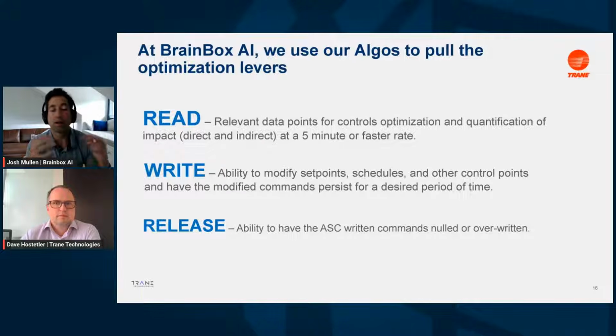And then finally, all advanced supervisory control should have guide rails, and it should have the ability to release control for whatever reason, whether it is internet connectivity, or some problem with the system as a whole, like the room temperatures are too hot, or there's a fault in the unit. You want to release the control to make troubleshooting really easy and give the control back to the BMS. And you can do that either by having the timed overrides just decay, or by nulling out the commands. It's dependent on what advanced supervisory control provider you're using or leveraging.